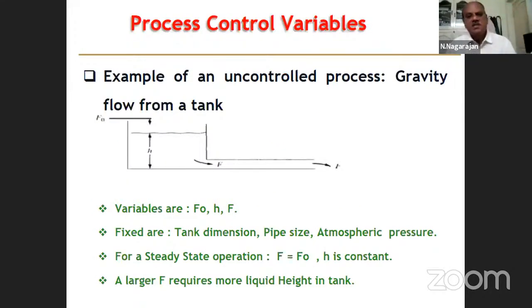So what are the process control variables? Let us take a very simple example of a tank, a storage tank, where you can see there is an input, FO, coming into the tank. There is a head developed and maintained in the vessel. Then the flow is going out from the tank. So FO is the input, H is the head, and F is the flow going out of the tank. Variables are inlet flow, head in the tank, and outlet flow.